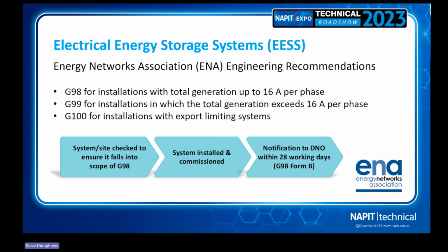If the system falls within the scope of G98, the system can be installed and commissioned, and you still need to notify the DNO within 28 working days, especially if you've got a combined system of solar PV and battery, and you're talking 32 amps per phase, then that's going to end up falling into G99. We know there's loads of installs out there that haven't been notified at all, but the way this is going with prosumers, the DNOs do need to know, and this feeds into our grid, making sure it's fit for purpose in this modern era of prosumers.